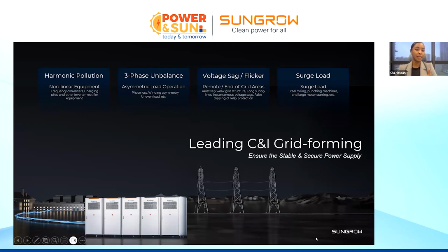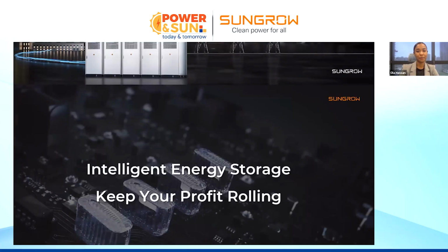So when we say grid forming, that means that this solution has a feature of forming a standalone grid. So if the grid even goes off, this system will establish its own voltage and frequency, and it will create its own grid. That's why we call this feature or function grid forming. So our PV inverters will continue to work and power will be injected to the C&I, which is the energy storage system, and to the load side as well, ensuring stable and secure power supply.